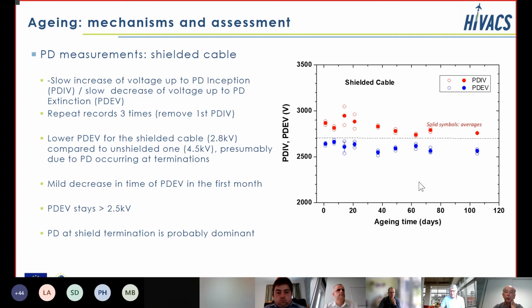If we switch to the PD measurements, these are the results obtained for inception voltage in red and extinction voltage in blue as a function of time for the shielded cable. We have inception voltages above 2,700 volts, and there is no significant evolution as a function of time. Second point is that compared to the unshielded cable, we have a relatively low PDIV, and we suspect that there was a limit here, in that the discharges were probably occurring at the termination of the cables.